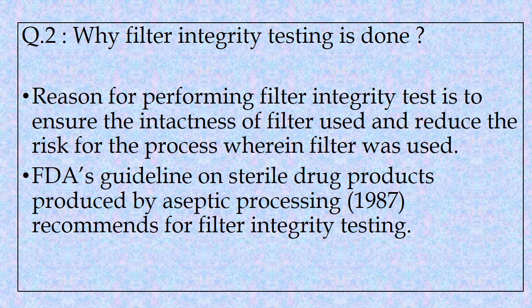Question 2: Why is filter integrity testing done? The reason for performing filter integrity testing is to ensure the intactness of the filter used and reduce the risk for the process wherein the filter was used. The FDA guideline on sterile drug products produced by aseptic processing (1987) recommends filter integrity testing.